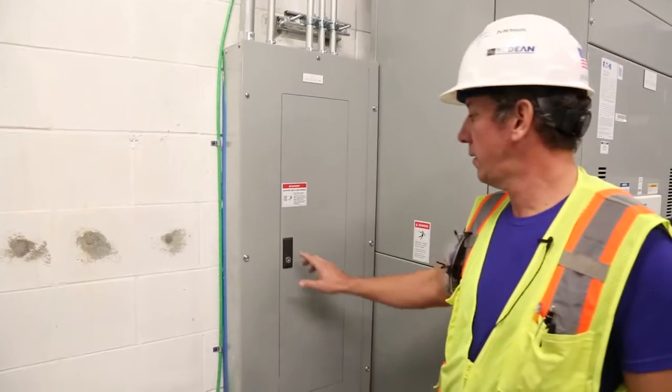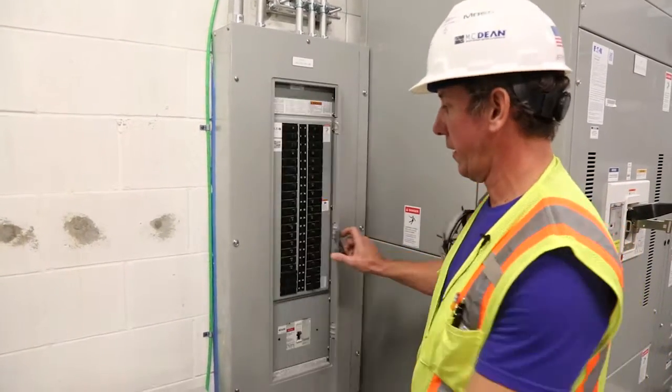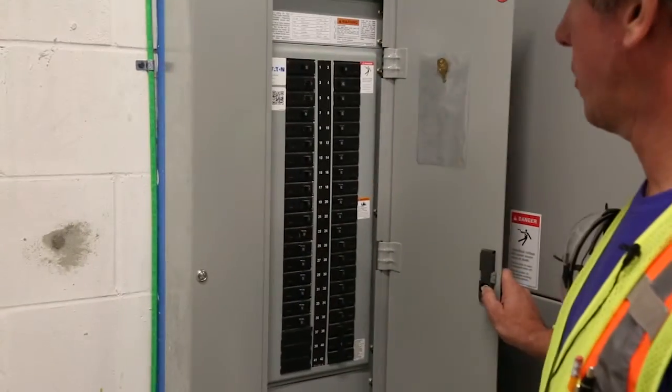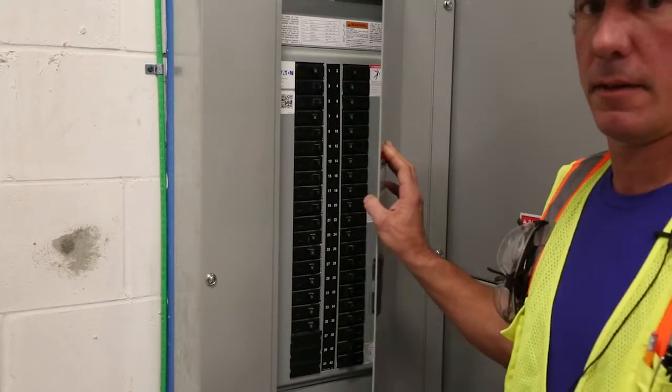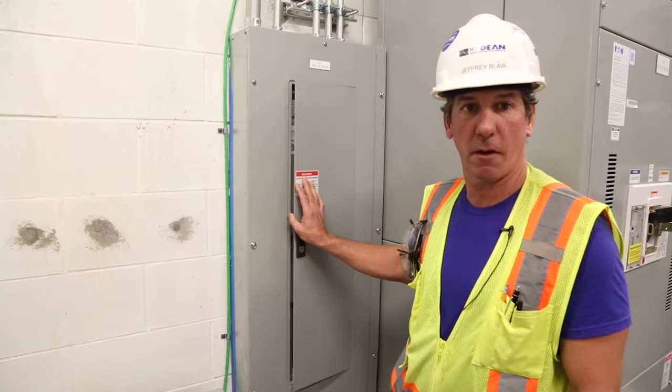All right, HPL is fed from HPH right next door. This is your 120/208 side. And this primarily just feeds receptacles, low voltage exhaust fans, and other things of that nature on this floor and down on level 50 as well.